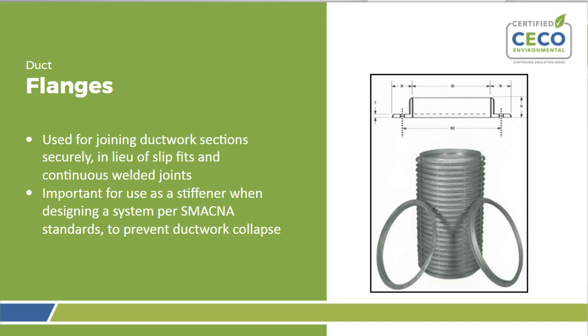The problem with continuously welded joints is a lot of times this ductwork is 20 feet in the air. You don't want a guy in a basket lift up there trying to weld the complete circumference that far off the ground. And flanges are important for use as a stiffener when you're designing a system per SMACNA standards to prevent the ductwork collapse.